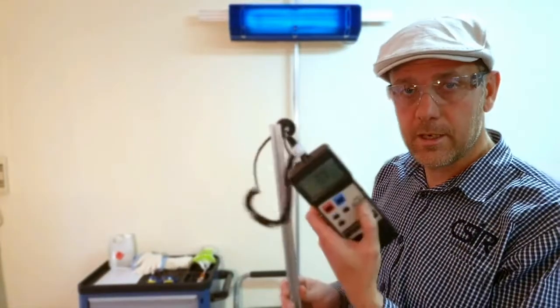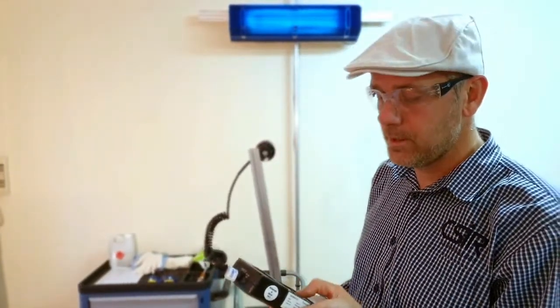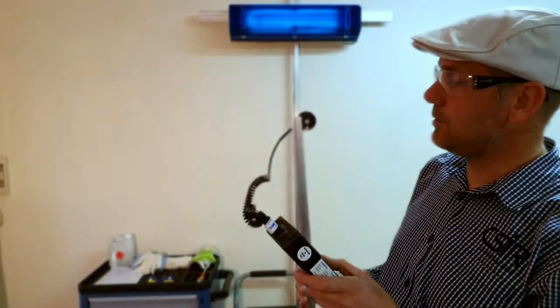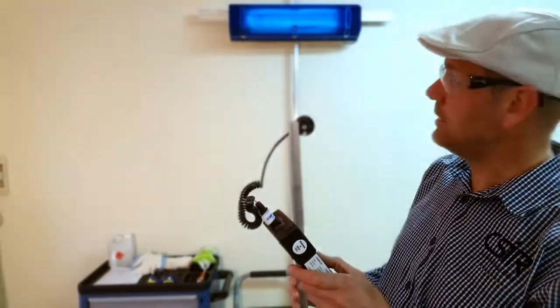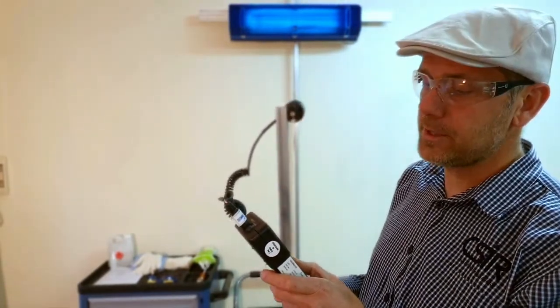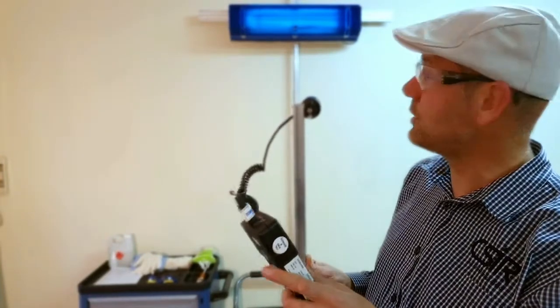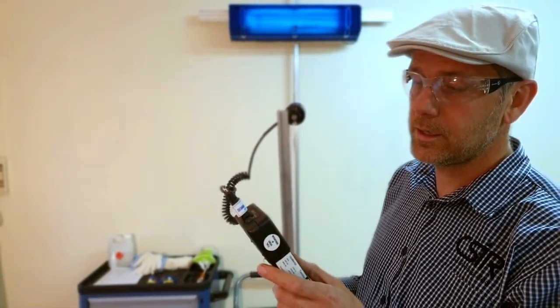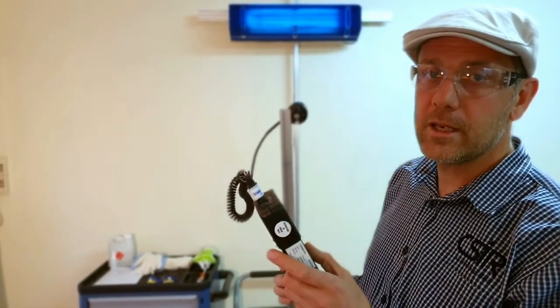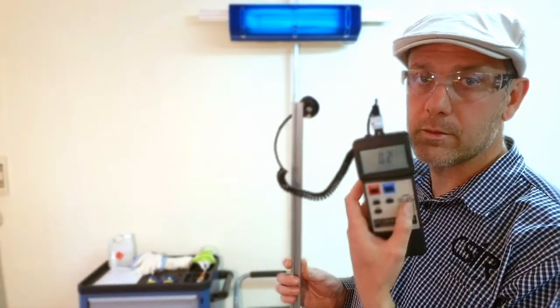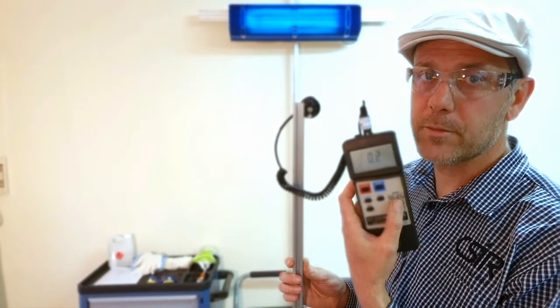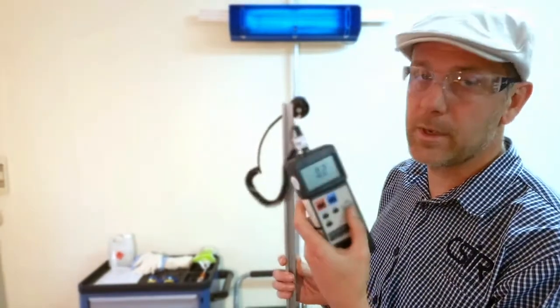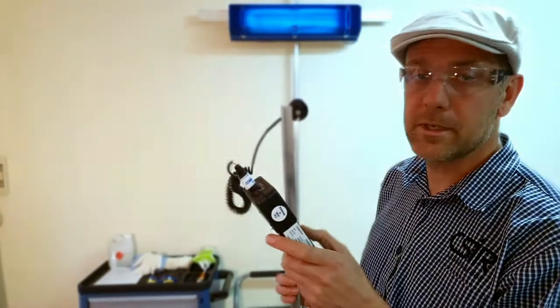So what we do is we select the correct range on your radiometer because we want accuracies of better than 0.1 microwatts per centimeter squared. And then we hold the sensor at eye level, 1.7 meters normally. I'm a little bit taller than that myself. And then point the radiometer from there at the UVGI device. And what we're hoping to achieve is a measurement of not more than 0.2 microwatts per centimeter squared. So for this installation, at this distance anyway, this seems like a safe environment.